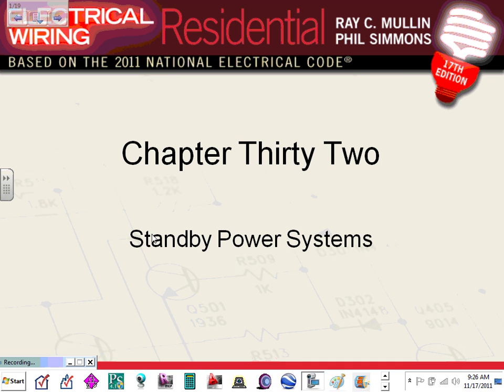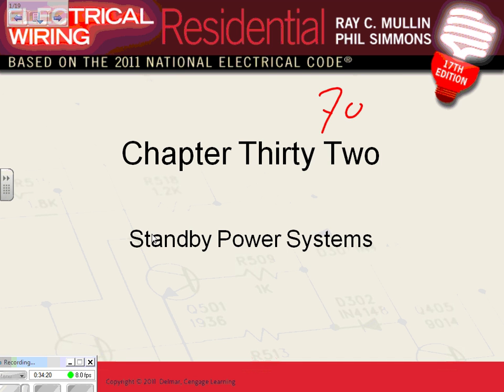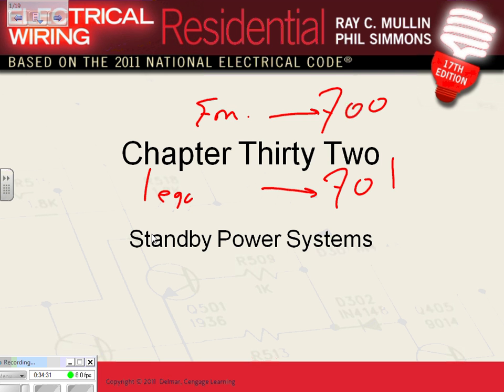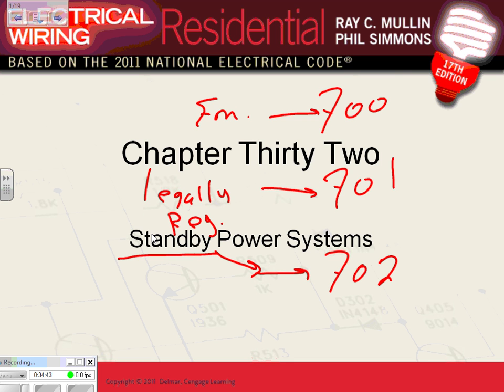The code talks about this, we'll talk about this one later, which is Article 700 in the NEC code book. There's another, Article 701. This is the legally required system. We're not going to talk about these two. And the last one, guys, is 702, which is standby. That's my standby. So there are three systems in the NEC code book that you can back up your building with.